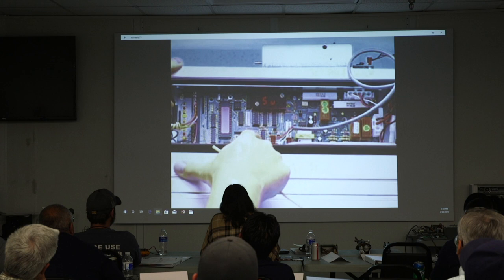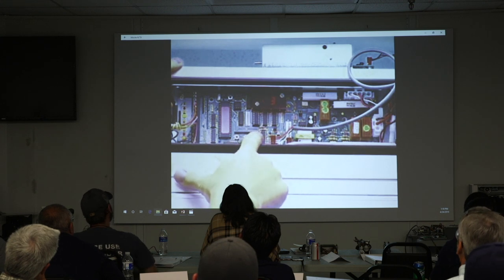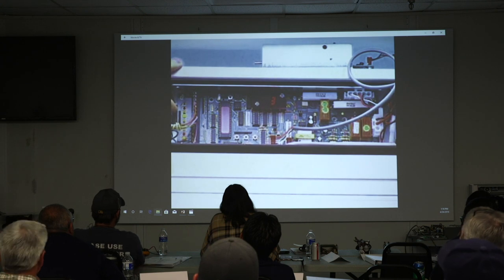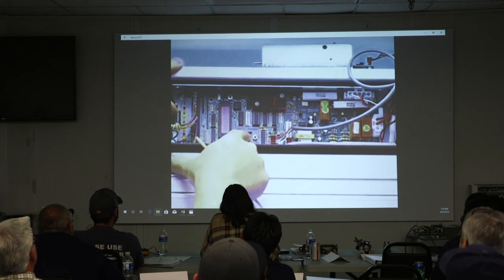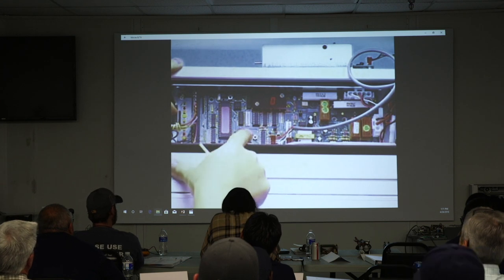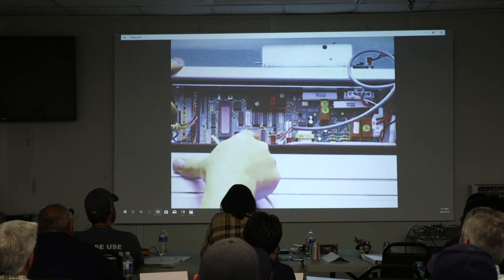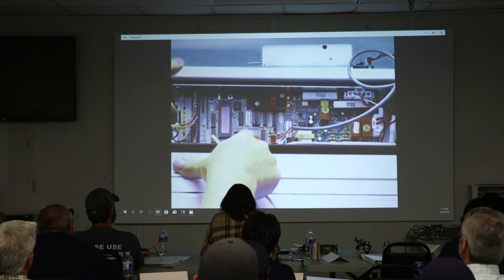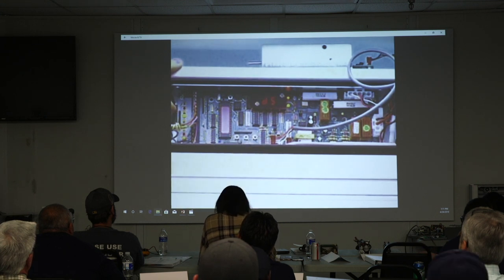TY will show briefly, followed by a 3, which is the factory default for this parameter. Press the down button until 0 appears. That determines the program will be set to linear drive. When 0 is displayed, press the set button. The lock light will turn on, followed by lock monitor if a fail secure lock is present. Control will display SE, followed by DS for data save.